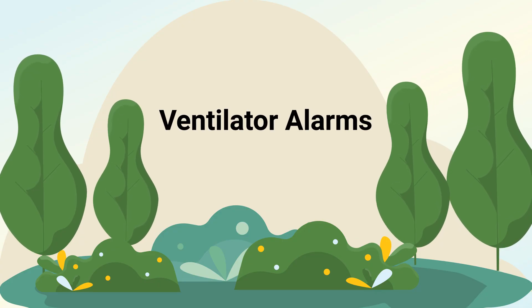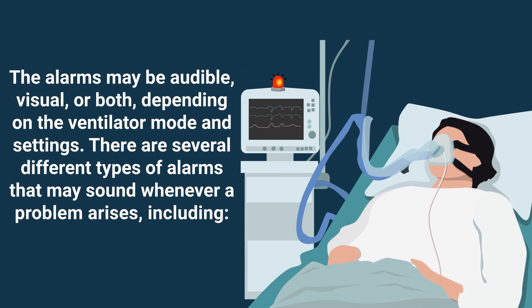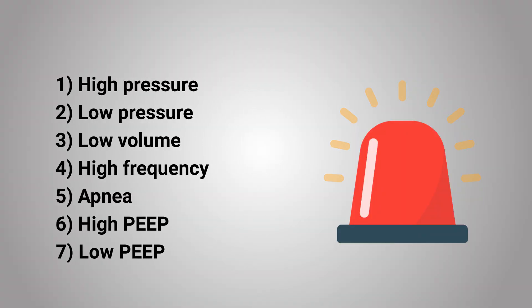That leads perfectly to the next problem: ventilator alarms. Ventilator alarms serve as a safety mechanism and use a set of parameters to provide alerts whenever a problem arises in the patient-ventilator interaction. The alarms may be audible, visual, or both, depending on the ventilator mode and settings. There are several different types of alarms that may sound, including high pressure, low pressure, low volume, high frequency, apnea, high PEEP, and low PEEP.